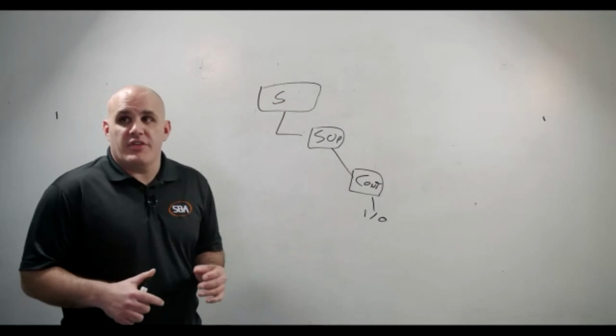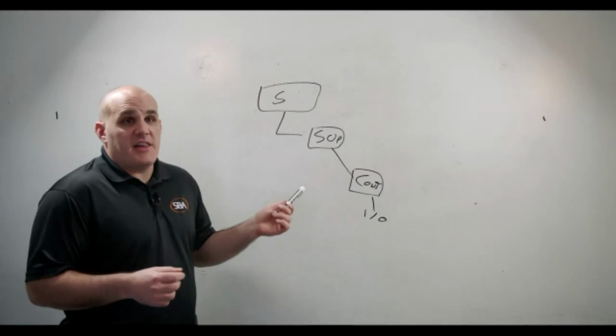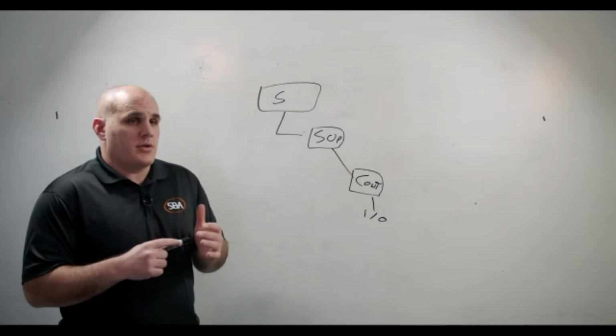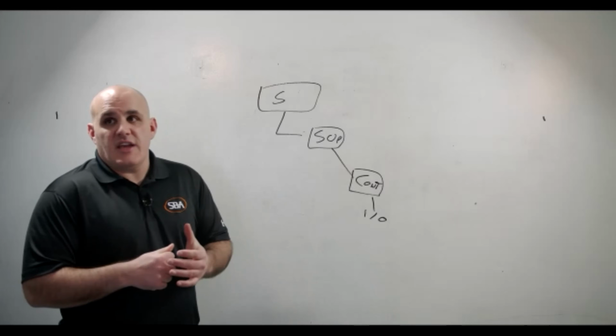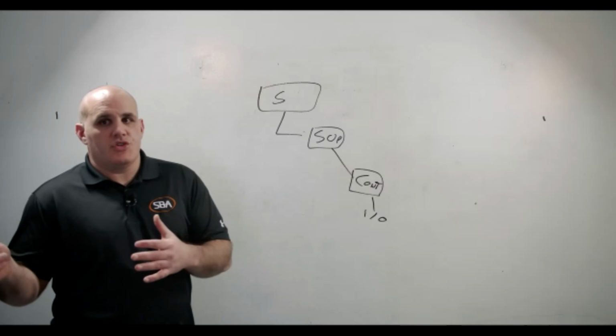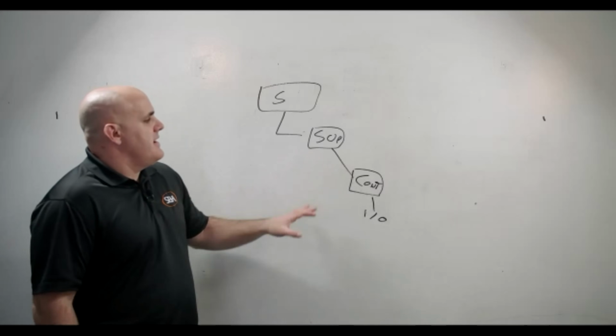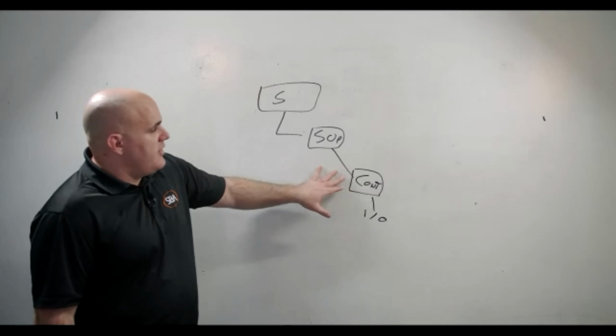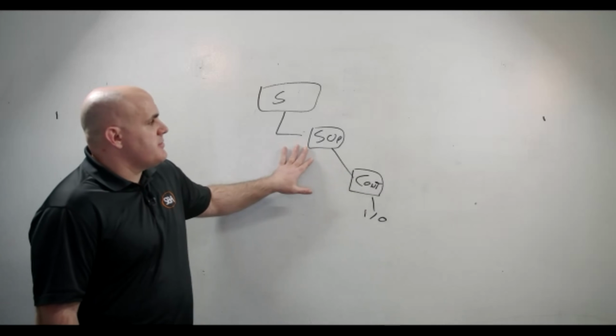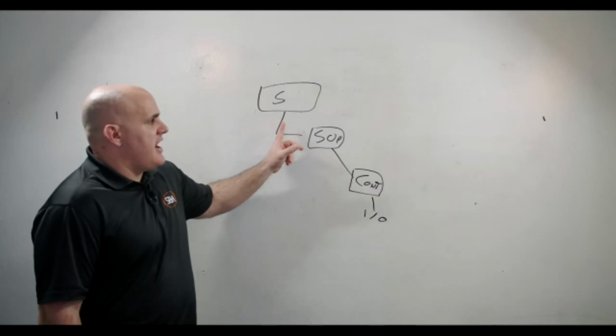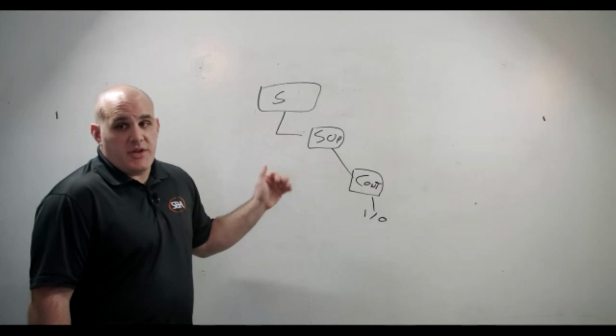So if I was doing DALI or DMX or KNX or any of those kind of lighting controls protocols, I would start with my IO, move to my space controller, move to my supervisory device, and obviously troubleshoot the network components in between.